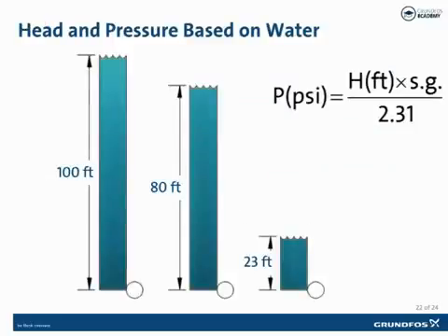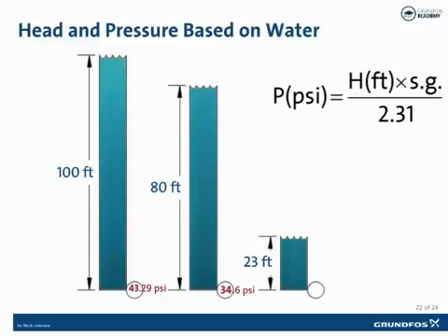To practice: if we had a column of water 100 feet tall, a pressure gauge at the bottom would read 100 divided by 2.31, which equals 43.29 PSI. For a column of water 80 feet tall, that would be 80 divided by 2.31, giving us 34.6 PSI. For a column of water 23 feet tall, that would be 23 divided by 2.31, giving us roughly 10 PSI — or more precisely, 9.957 PSI.